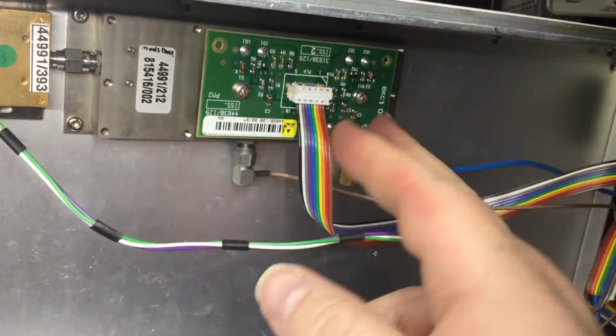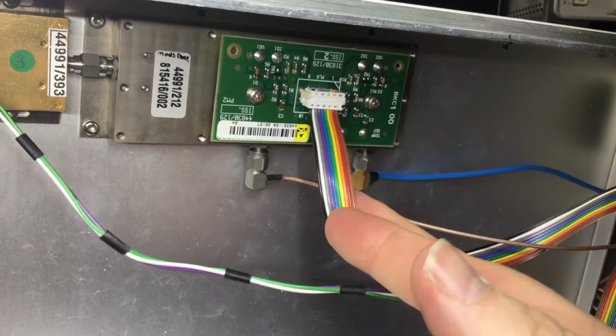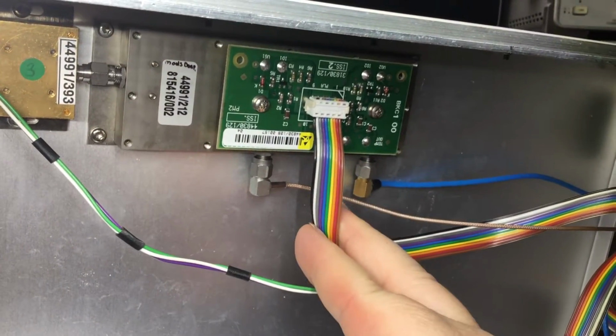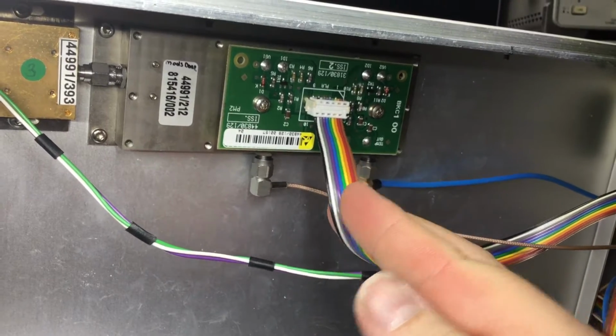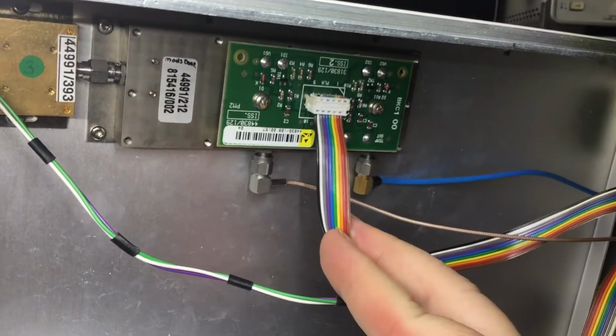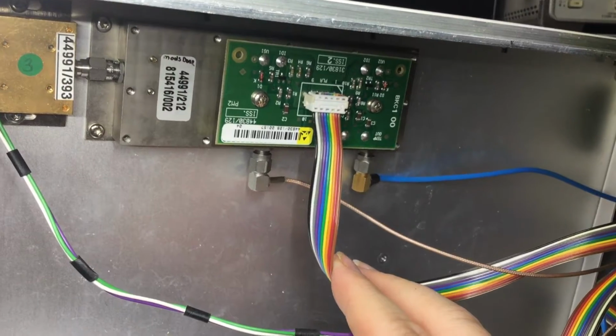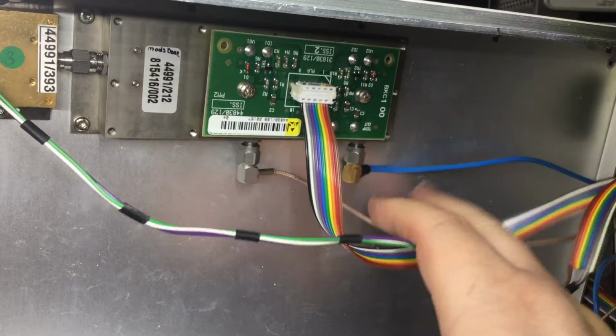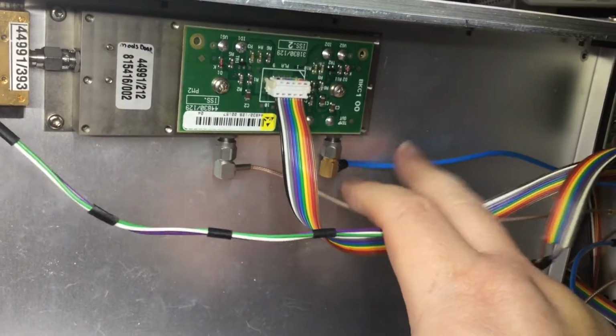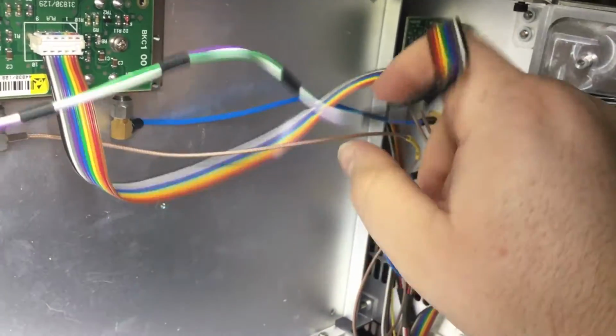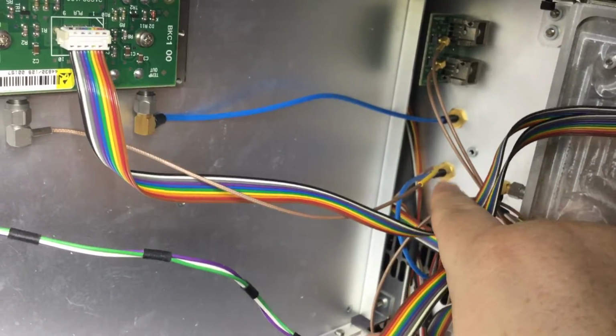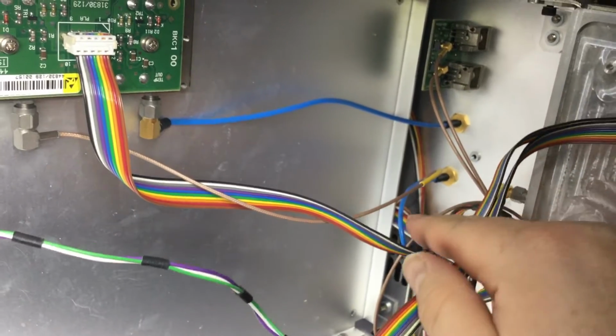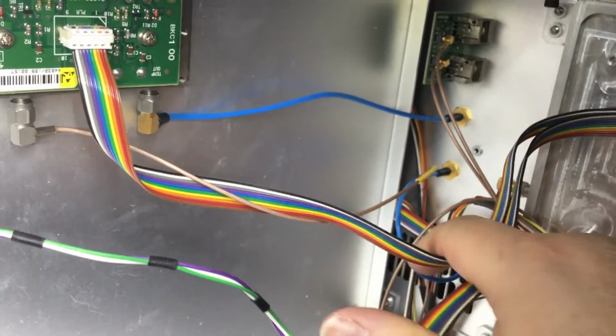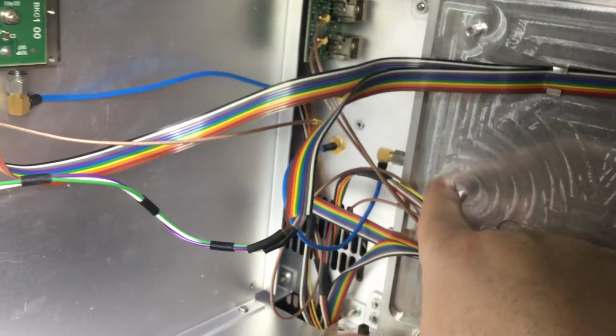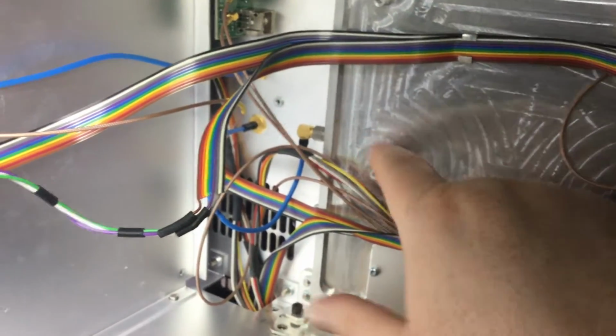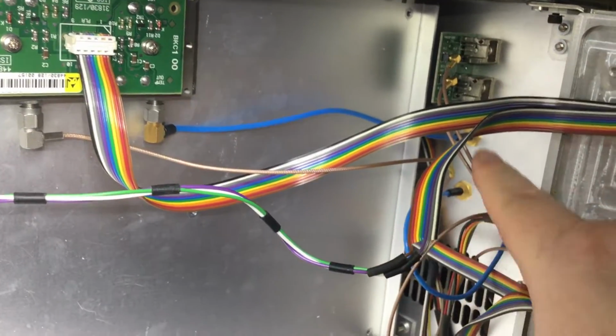This module here, it looks like it's programmable. We've got the data loom connecting to it, which will carry supply, serial clock, serial data, and ground. We've got 2 RF. This blue cable goes out to the back of the instrument down there on the back panel, and then there's a link through to this next blue cable here, which then goes off to obviously this module that we've just hinged out, that we've been looking at. So that's the IF link.